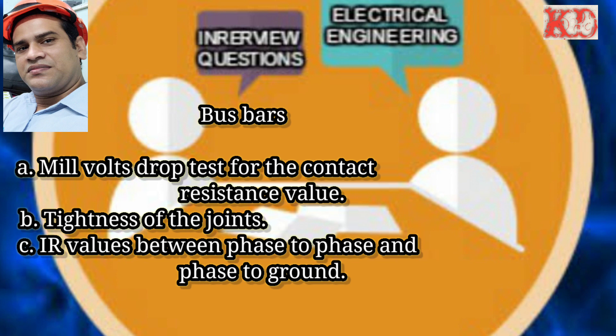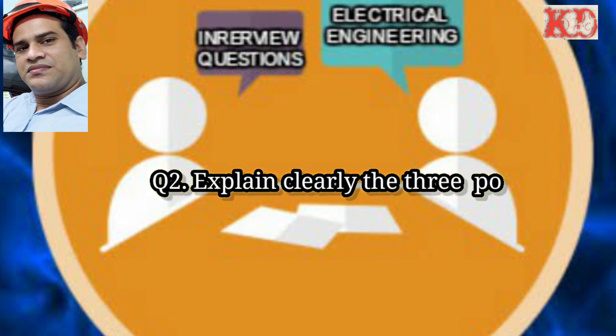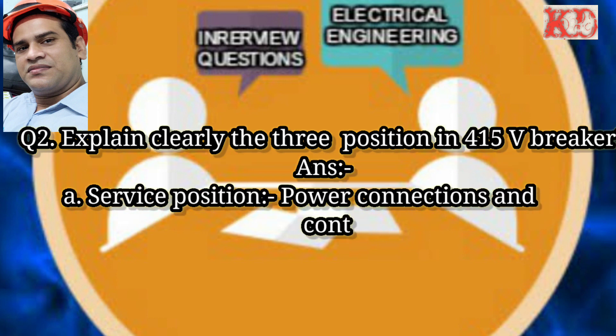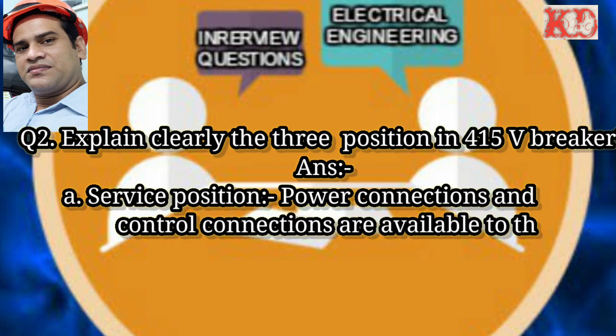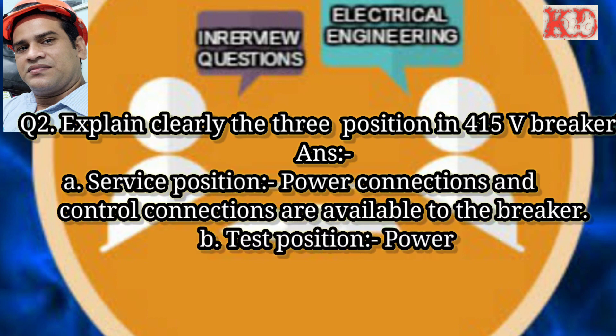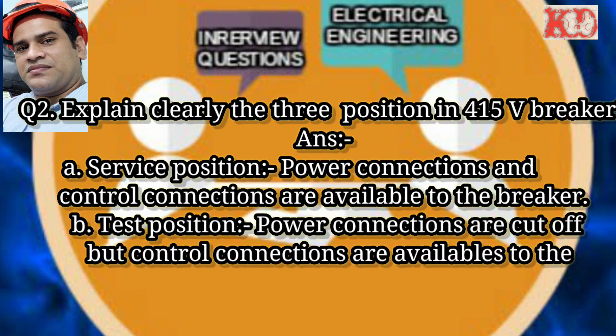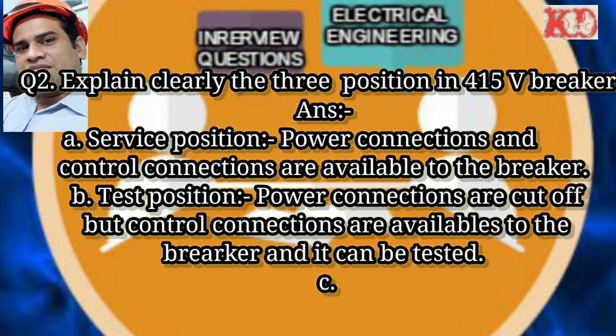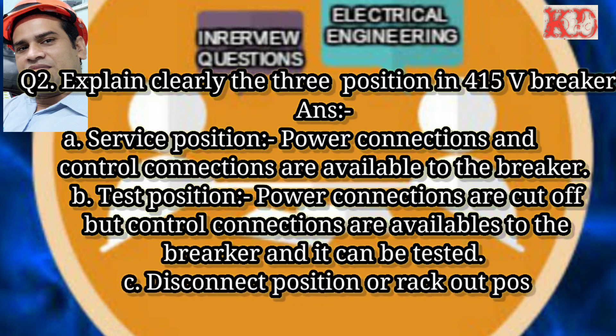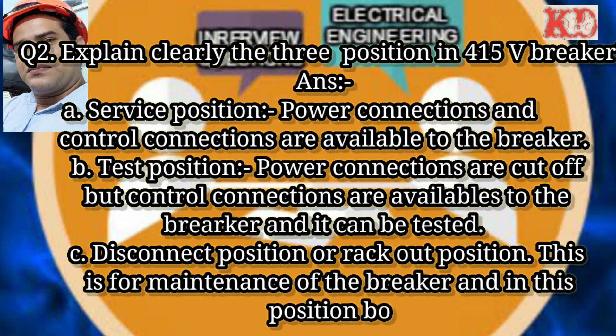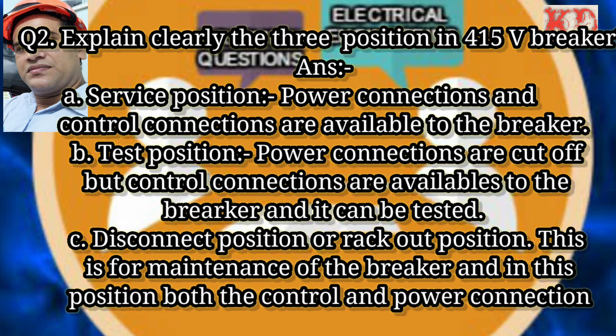Question number two: explain clearly the three positions in a 415V breaker. Answer — first, service position: power connections and control connections are available to the breaker. Second, test position: power connections are cut off but control connections are available to the breaker, and it can be tested.